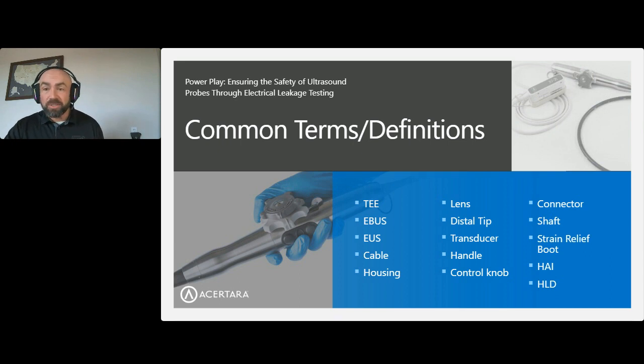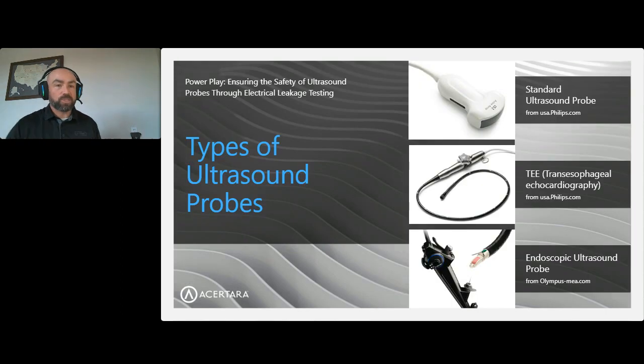There are buttons to be able to steer the array so that they can electronically, sometimes mechanically, shift the focus of the array. And then there's a couple of knobs on there that allow you to articulate the end of the probe, the distal tip, in two perpendicular 180-degree planes, so that you can basically manipulate it while it's inside the body to acquire the best image possible. All right, that's a lot of stuff to go through. I know it's a lot of stage to set here, but I want to make sure that we're all speaking the same language here. So let's talk a little about probes that are in use.